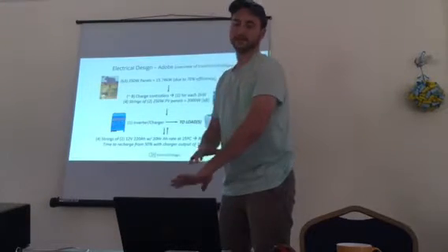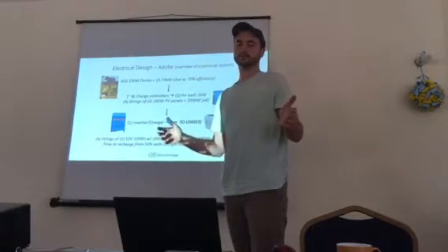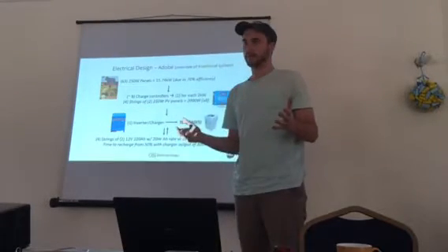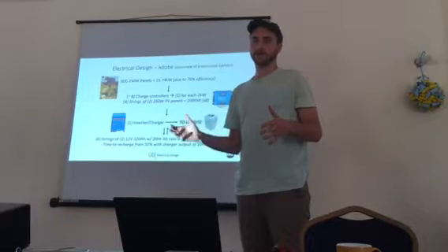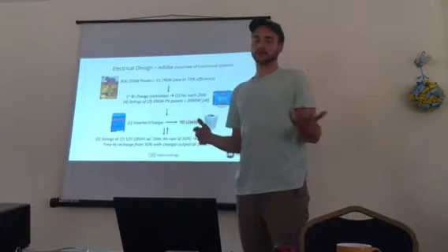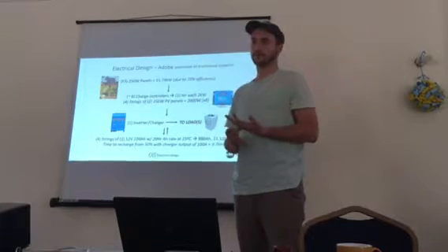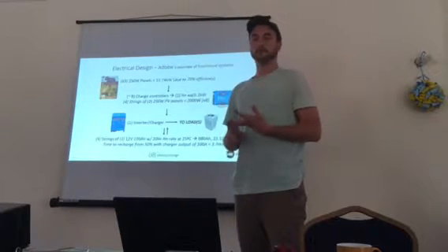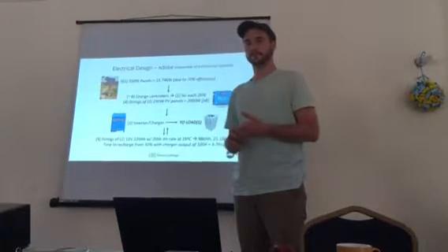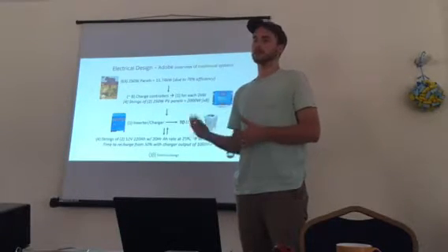And so what would that system overview look like? So you have your panel array, and then I'm speccing 8 controllers for the charging capacity, about 2,000 watts per controller, to better charge our batteries and also prolong the life of the battery, so you could get 5 years out of your typical AGM lead acid battery. And then also your inverter charger, which basically, speccing what you preferred there and fitting the system to that, would then go to your loads.